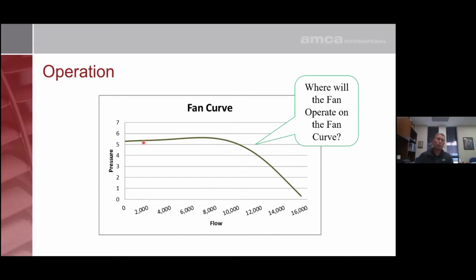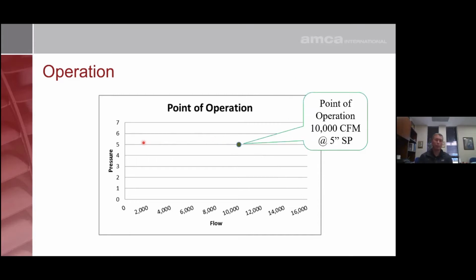So when a customer comes to us and says, hey, I need 10,000 CFM at 5 inches of resistance, what they're really saying is that they have a system that if you push 10,000 CFM of air through that fan, you are going to generate 5 inches of resistance. And when you look at that system, there's a number of points that can represent how that system is going to perform. And just like with the fan curve, there's an infinite number of points.